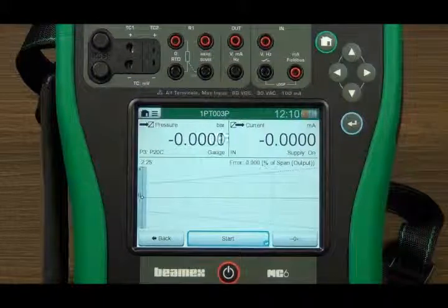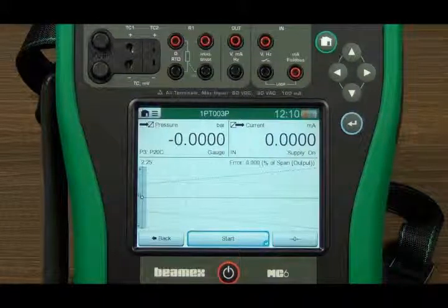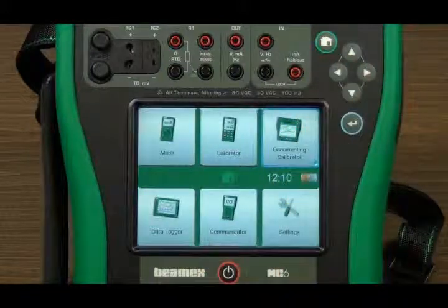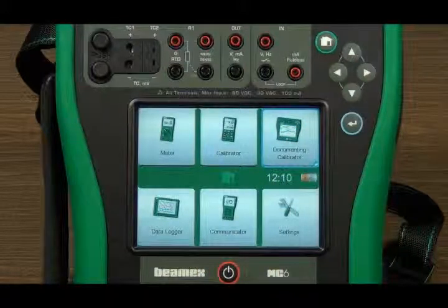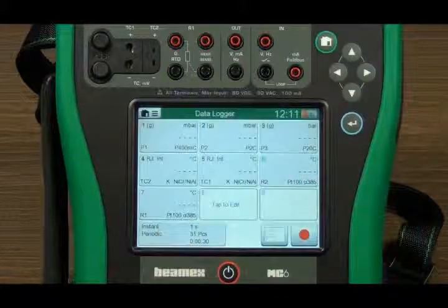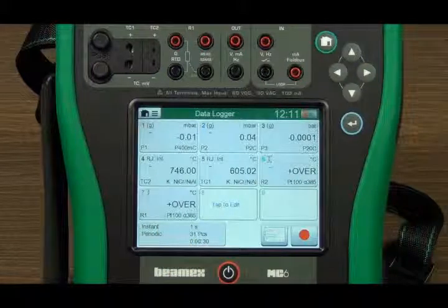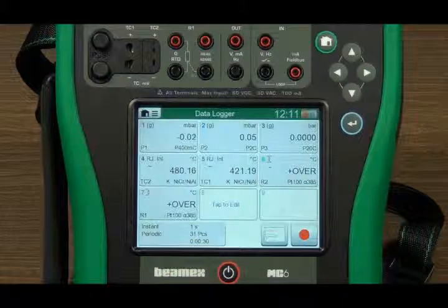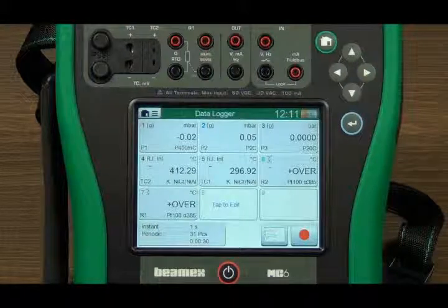When the calibration is done, you can store the results in the calibrator's memory. You can then upload the results to Beamex's calibration software at a later time. Data logger. The purpose of the data logger is to log various measurement signals. It works as a paperless recorder.